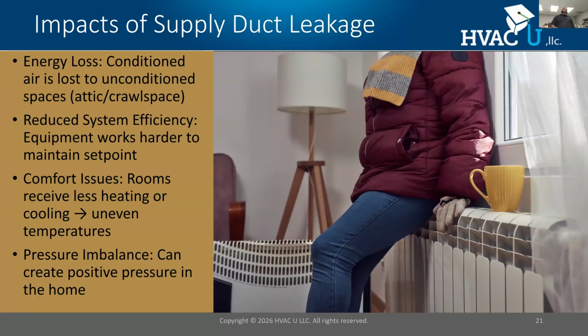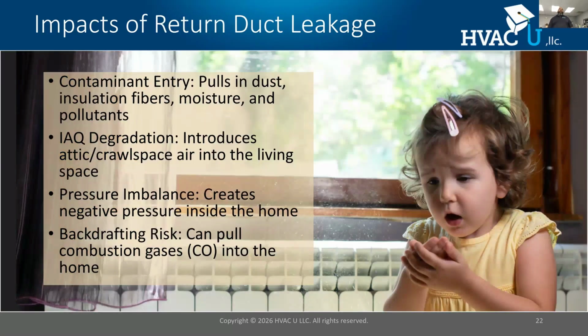All right, so duct systems that leak reduce system efficiency. They can also cause some comfort issues. All right, and then lastly, they can cause building shell imbalances. We'll talk about that. All right. If we look at the return side, it is even more diabolical. It's pulling in air from unconditioned space. So we have a vented attic or crawl space.